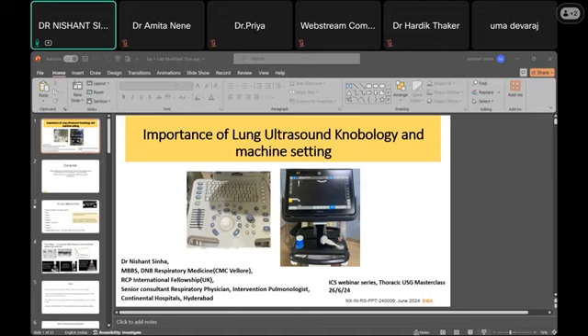So it can see deeper structures better. If you see the linear probe, it has got high frequency and it can only see superficial structures. And if you see curvilinear probe, again, it has got wide footprint. That means it can see a little wider, but at the same time, it can see deeper because it has low frequency. So if you see in the right side of this slide, there's a graph which is very, very, very basic and very important.